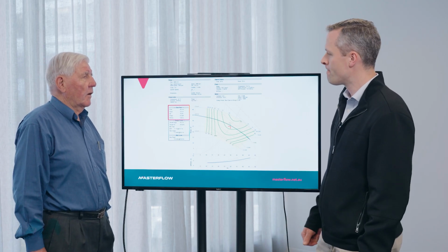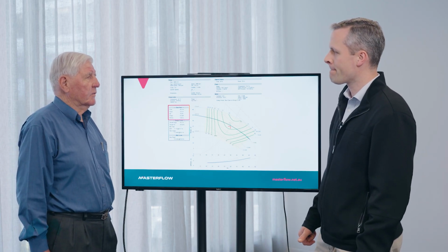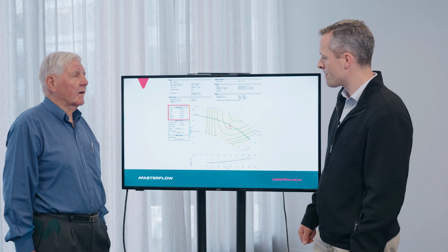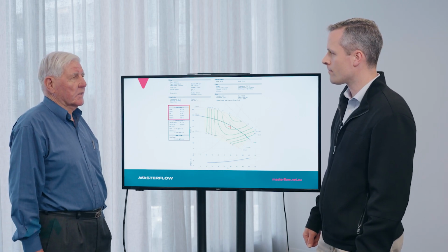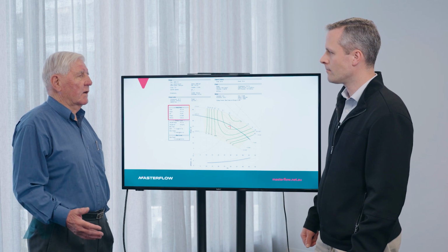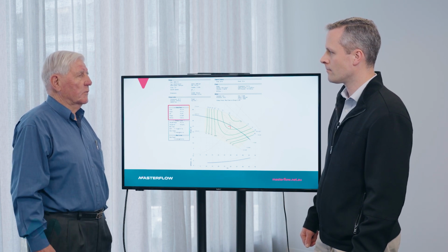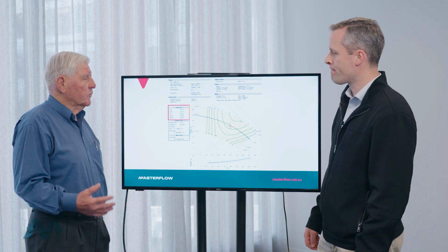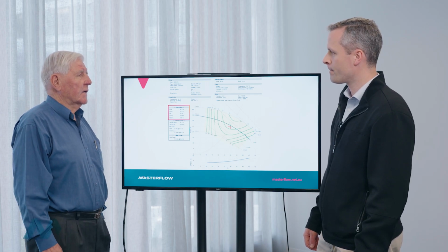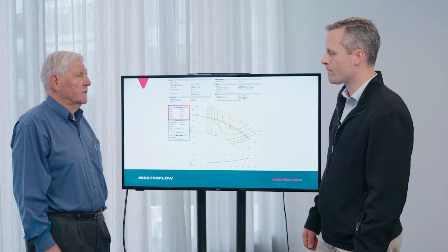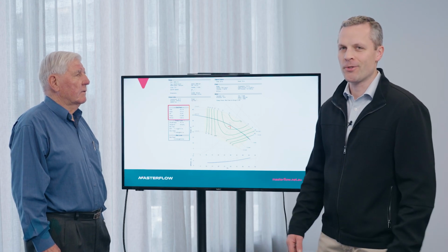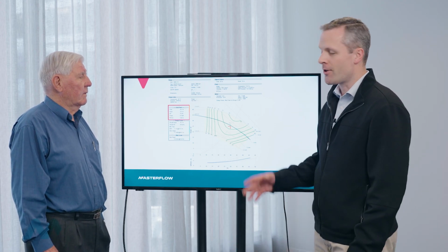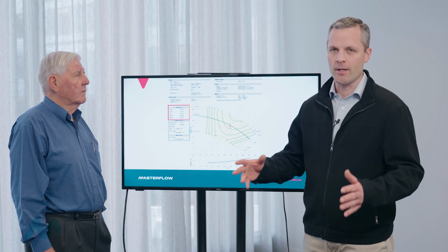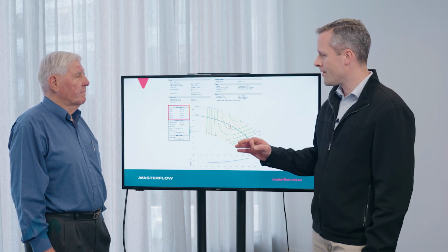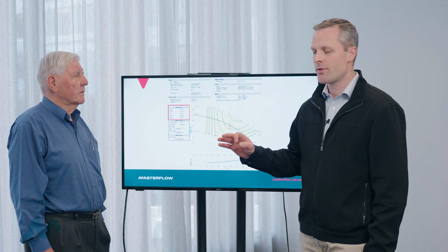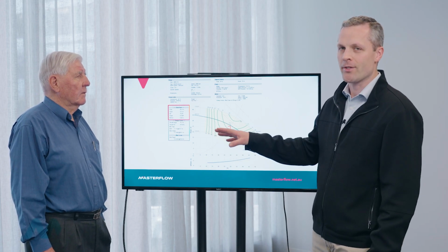Generally speaking, yeah. Obviously, you wouldn't have the same pump anyway if you're running at 1,450 because it would be a larger pump and you'd have larger suction connections. So everything in that regard is contributing to a more favourable situation. If you've got suction problems, very often a 2,900 RPM pump is not a good solution. Our recommendation to you as the contractor or the consultant is don't try to save money with a smaller pump, i.e. a 2-pole pump, and minimising your pipe work diameters. Design it properly, and this will save you a lot of hassle down the track.